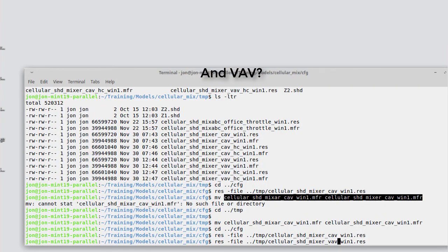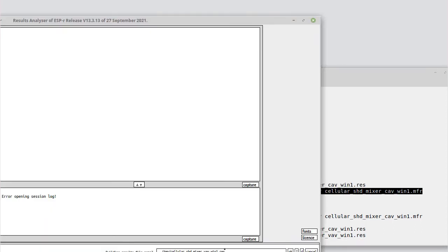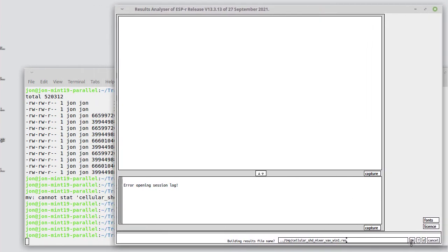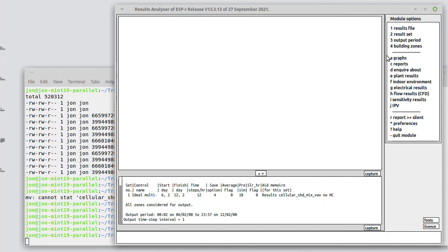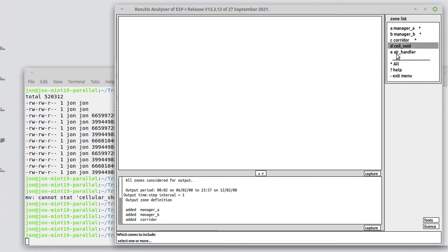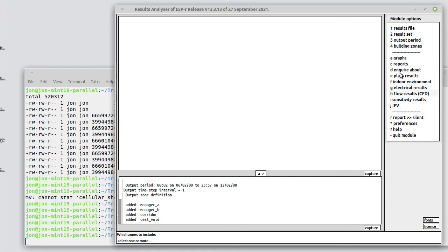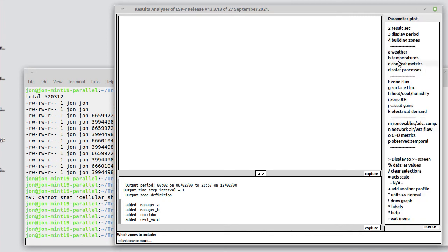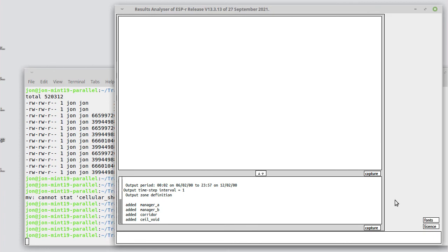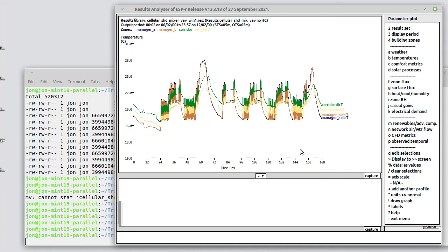So, what's the performance of the VAV? Now, the only thing that changed was the flow control logic, going from on-off controller to a proportional controller. So if we look at the temperatures in the rooms, we again have some ratcheting. It is somewhat different than the other because we've got these 18, 21 degree set points and a 2 degree proportional band.